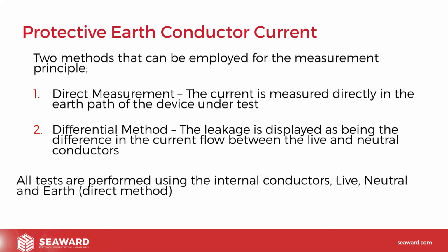So when we're talking about leakage tests or protective earth conductor currents, there's two different methods that a piece of test equipment can employ to perform the test. There's either what we call the direct measurement method, or there's what we call the differential method. Now, typically this won't really matter to you guys doing the test. This is more to do with how the tester performs the test, and it does it in one of two ways. There's either what we call the direct measurement.